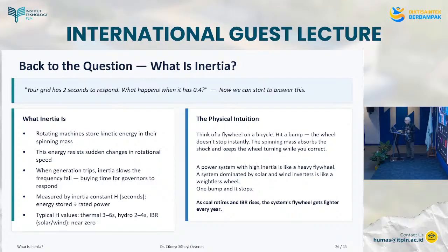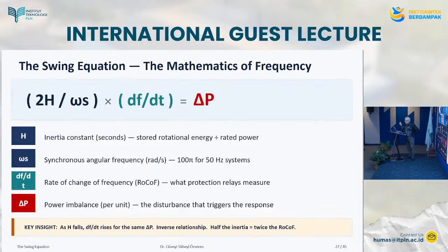When we are retiring coal and increasing wind and solar, system inertia gets lighter every year, so we have to find ways of replacing it. This is the equation you use to calculate the change of power, or the inertia constant of the system. What you should take away is that as H, the inertia constant, falls, df/dt rises for the same change in power. There's an inverse relationship: half the inertia causes twice the rate of change of frequency.